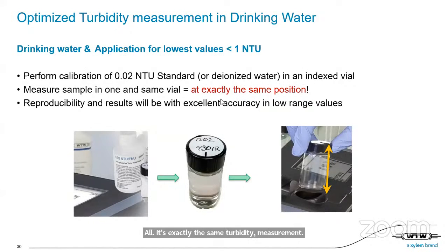For optimization in drinking water, because I think many of you are working in drinking water, the easiest way is to make the zero calibration with deionized water. For example, if you run out of calibration standard, mark a vial, dispose the water, fill in your sample, rinse it before, but fill in the samples and measure. Then you have the same vial for the same standard. You have the same influences, because glass is never homogeneous, so there are slight differences in glassware. So if you have the same calibration of the zero point, and that's the interesting point for drinking water, and use the vial for calibration and sample, you are top precise. That is hard to beat.